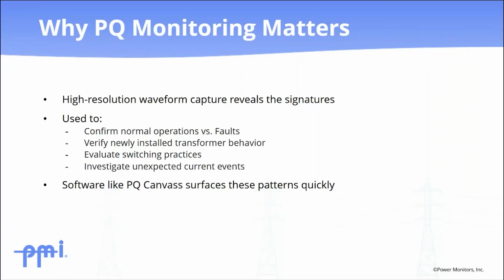The reason we can do all this confidently is that modern PQ monitoring captures the level of detail you need. High-resolution waveform recording lets engineers examine the exact shape of the current and voltage during the switching event. That's how PQ data gets used to confirm that a disturbance was a normal system operation, not a fault, verify the behavior of newly installed transformers, evaluate switching practices on a feeder, and investigate unexpected current events. Software like PQ Canvass is what brings these signatures forward quickly so you don't have to comb through the entire recording by hand to find them.